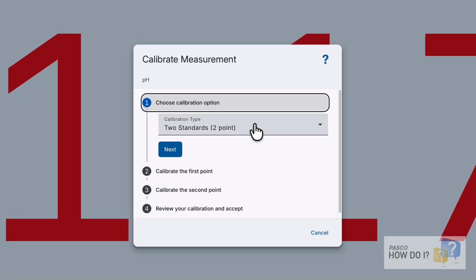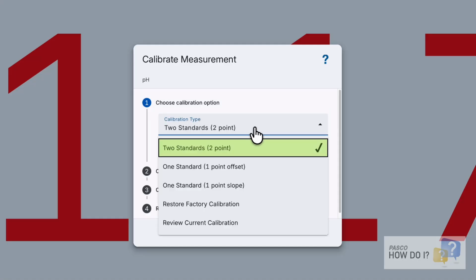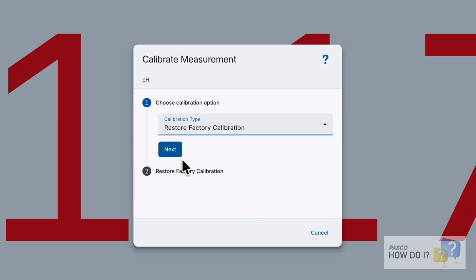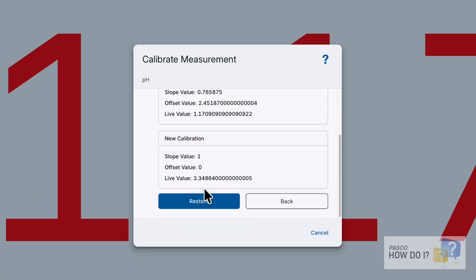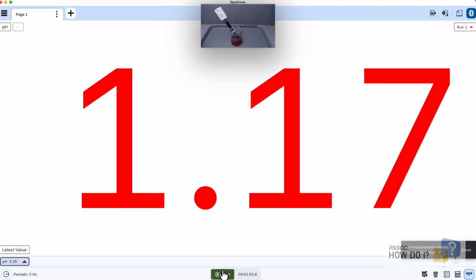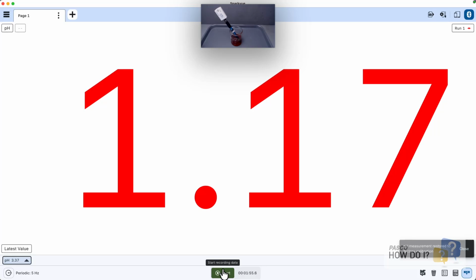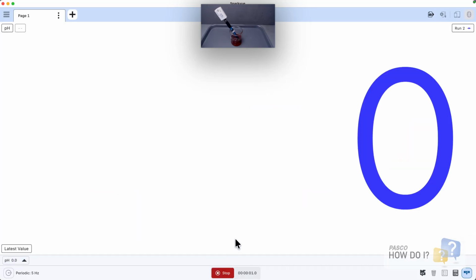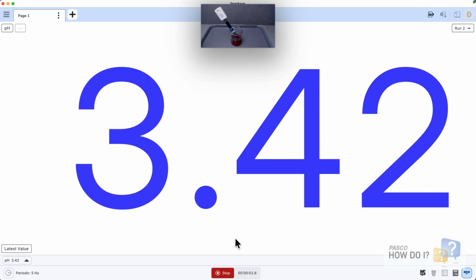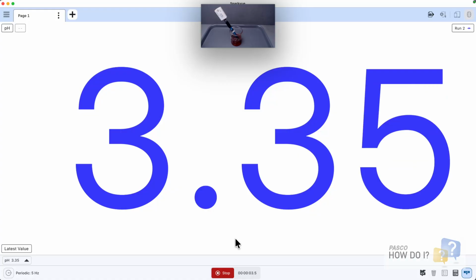We want to switch the calibration type from the actual process of calibrating, in this case for the pH 2 standards. So I'll click the calibration type drop-down, and I'm going to select the option to restore factory calibration. I'll choose Next and Restore, and it will reset the sensor to its factory defaults of calibration. So now when I press Start, I get what I think is a more reasonable value for the pH of this solution.